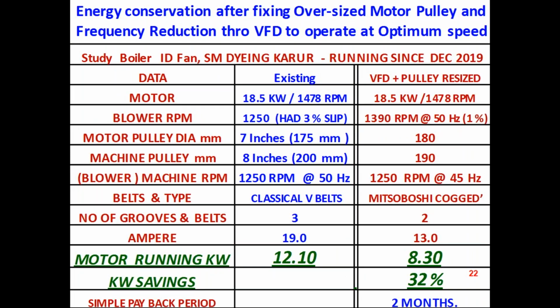A typical example on a variable torque load is a blower, an ID fan blower for a boiler. Here the operation is very critical. The ID fan has to give an induced draft static pressure critically, and it is maintained by doing these changes in the motor and machine, especially on the pulley and belts. Automatically, this industry achieved almost 32%. You can see on the fifth line, the machine RPM is kept at 1250 RPM at 50 Hertz before, and the same 1250 RPM was operated at 45 Hertz. Straight away, a 10% reduction in speed gave almost 30% reduction in the power. So this is possible with better belting, optimized belting and optimized pulley ratios. Next, please.